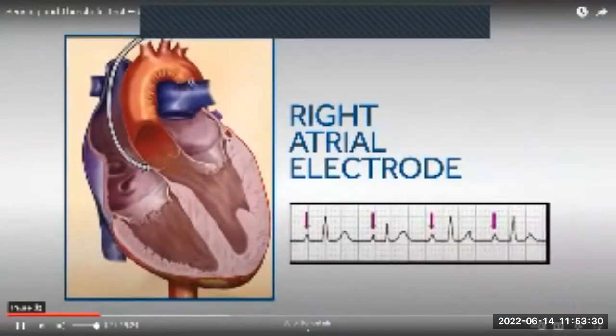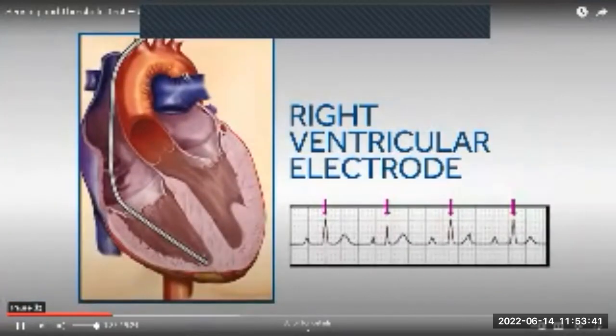Appropriate sensing results in every heartbeat being properly sensed. This means that when the lead or wire is located in the atrium, all P waves are sensed, and when the lead or wire is located in the ventricle, all R waves are sensed.